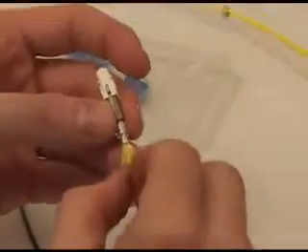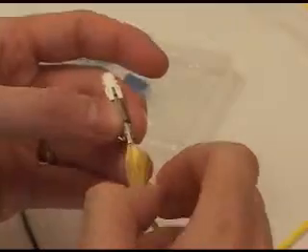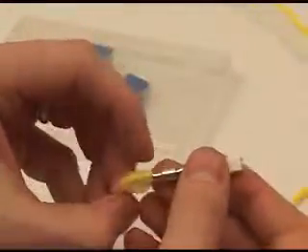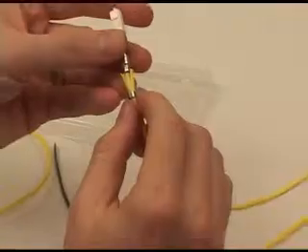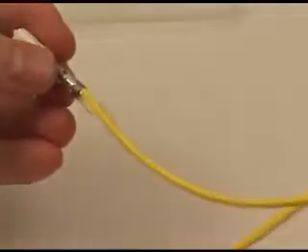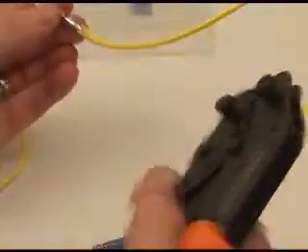Now remove the 3mm cordage from the stop ring. Next slide the final crimp ring into position, which will secure the 3mm cordage. This will add additional strength to the strain relief. Now using the .178 hex die on the crimp tool, complete the last crimp, which crimps the 3mm cordage to the main body.